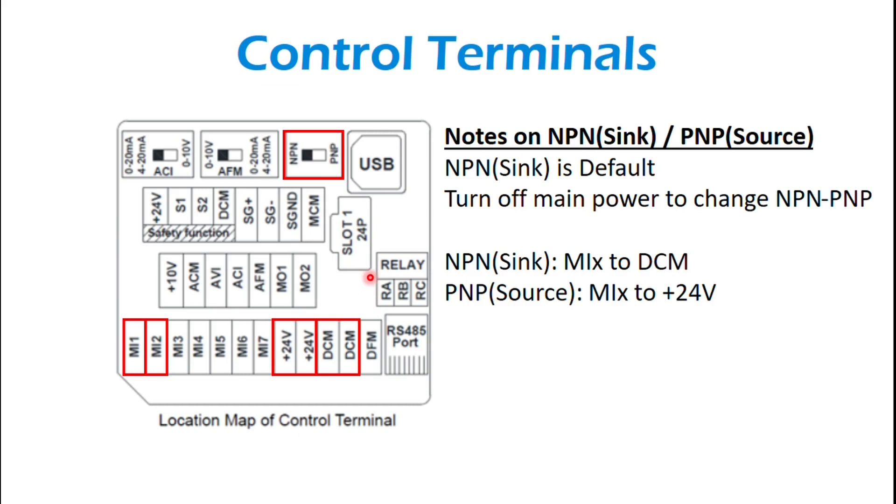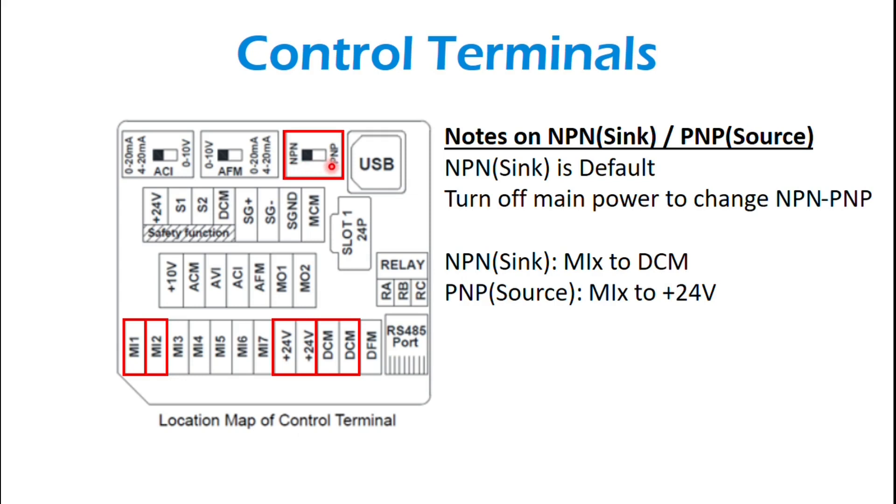And a little bit more on the control terminals. So you can do sinking or sourcing. So by default, this DIP switch that's on the control board is switched over to NPN for sink. And if you need sourcing, you can do it. Just flip your DIP switch over, turn the power off to the drive before you do that.